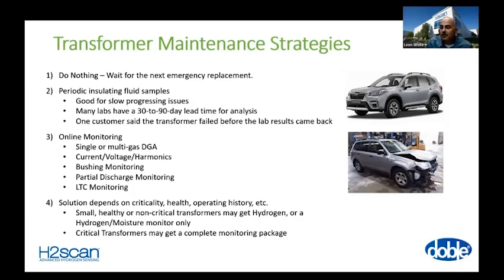forget about them. Being such a critical component, and one that's certainly harder to get, going back to Moses' presentation again, online monitoring is a great strategy to employ to have the transformer let you know when there's a problem, so hopefully you can fix that problem before the transformer fails. What's also very popular, as Moses indicated, is periodic insulating fluid samples. We've moved away from the term oil sample as we move into alternative fluids, the esters and so forth, so now we're calling them insulating fluids. Typically people are taking those once a year, probably on average. For critical units, a lot of people will sample quarterly.